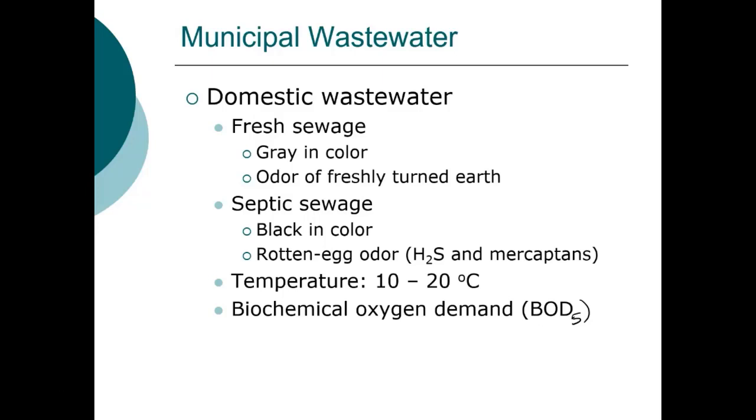The point where it flows into the Red Cedar is not a very large body of water. So we need to make sure that the biochemical oxygen demand, or the amount of organics present in the water, that when the microorganisms degrade that, consume oxygen, is not to the point where it will have a detrimental impact on the body of water.